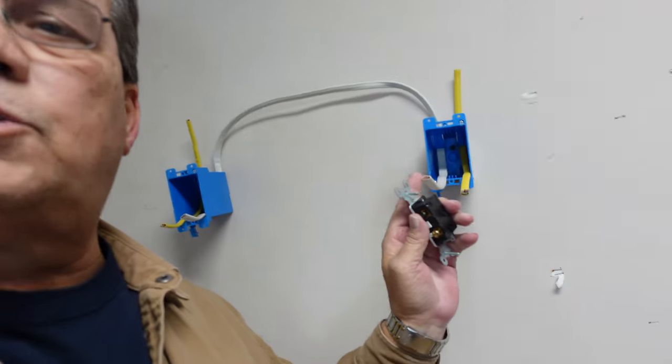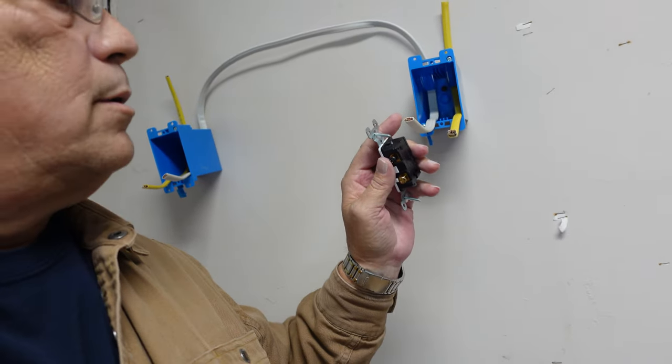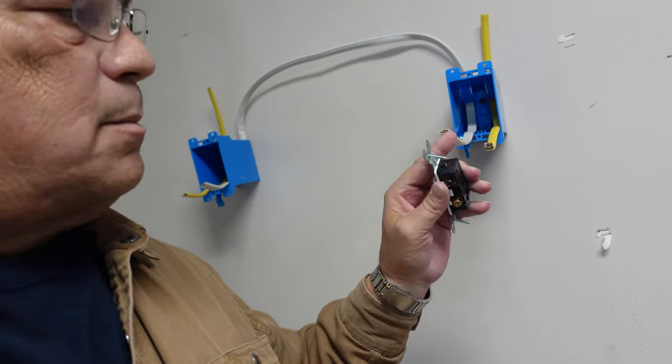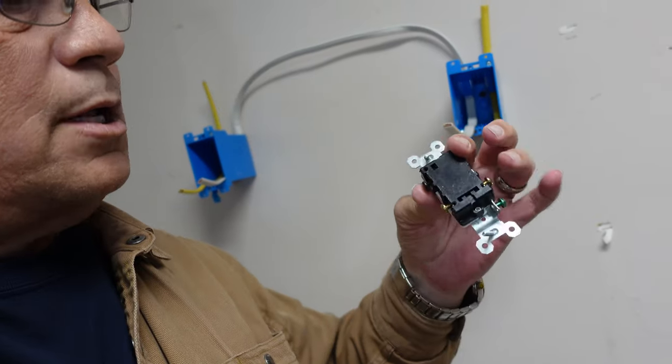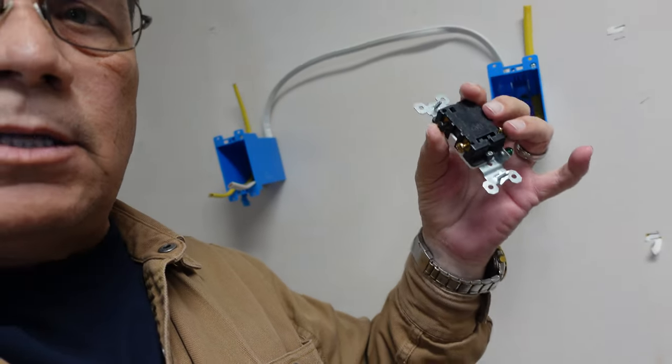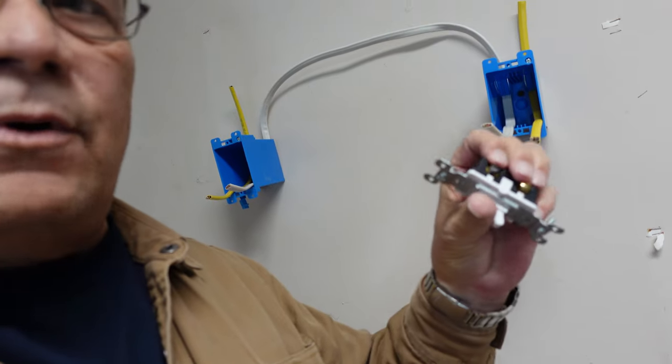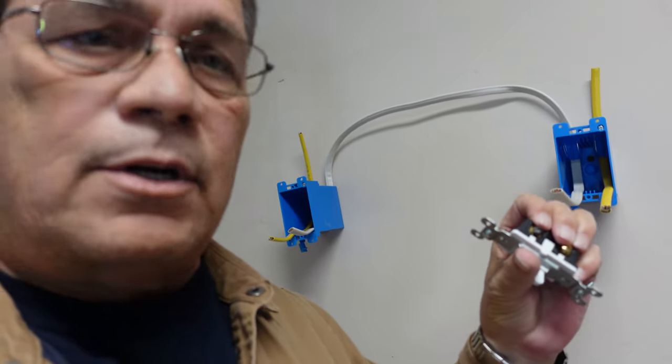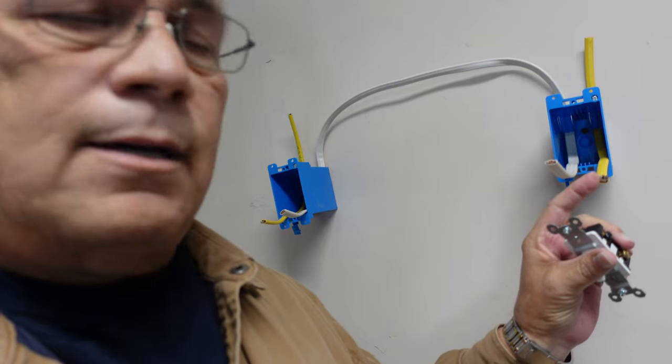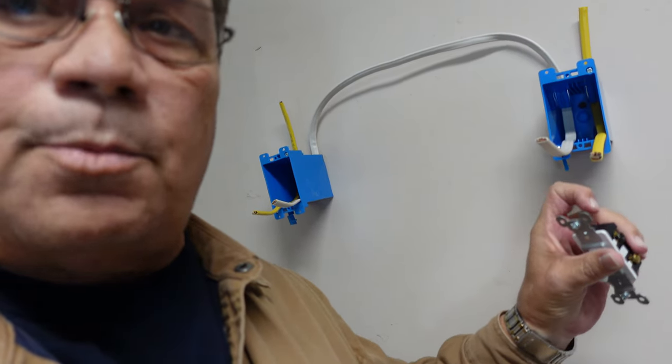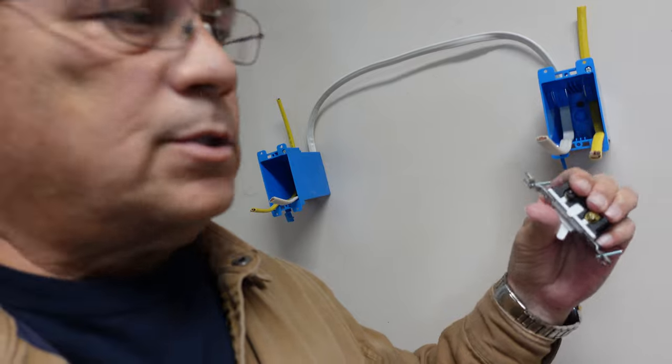Now when you are hooking your switch to the travel legs, it doesn't matter black or red what goes on the brass, as long as you're putting travel legs on them. You do however need to, it does matter however, the hot leg going to your light fixture or from your breaker. It matters that the black leg goes to your common. I hope I'm making sense to you here.